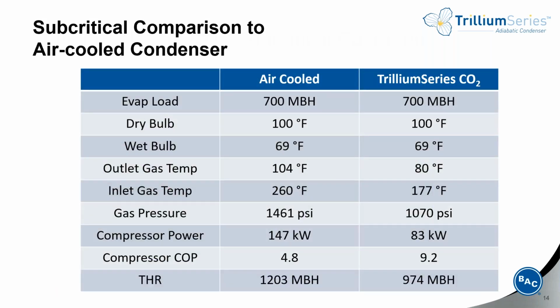We can look a little bit more closely at this 700 MBH example. You can see that with conditions of 100 degrees dry bulb and 69 wet bulb, the Trillium adiabatic product is still able to achieve CO2 gas outlet temperatures of 80 degrees. Whereas with an air-cooled system, the gas outlet temperature would be 104 degrees. This results in over 40% savings in compressor power. And this really highlights the benefits and the advantage of using an adiabatic type cooler in a CO2 system compared to a traditional air-cooled.